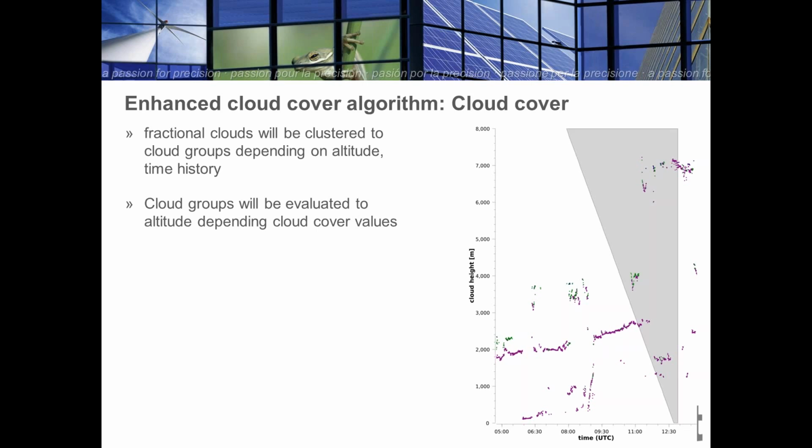You see again this cloud height, and you see the time, and some of these dots are clustered to, let's say, a cloud type, combined here into a cluster. So there is a statistic over 10 minutes to half an hour or several hours at high altitudes, which comes close to the meteorological observer, who looks into the sky and decides there are, let's say, 5/8 cloud cover levels. Then the instrument tries to simulate it and do the same job and compare these results.